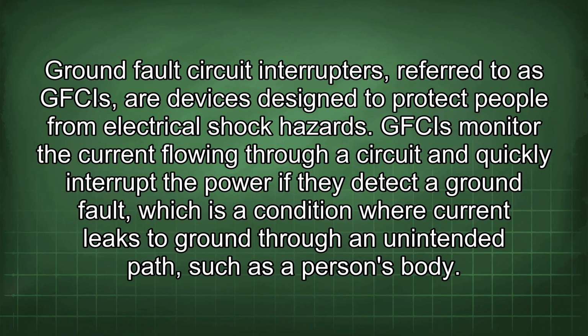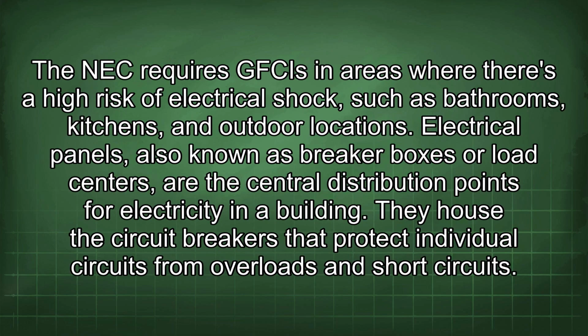GFCIs monitor the current flowing through a circuit and quickly interrupt the power if they detect a ground fault, which is a condition where current leaks to ground through an unintended path, such as a person's body. The NEC requires GFCIs in areas where there is a high risk of electrical shock, such as bathrooms, kitchens, and outdoor locations.